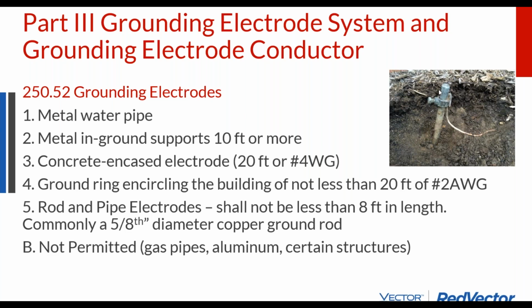These ground rods are 8 feet, 10 feet long. 8 feet needs to be in the ground. So that's a lot of copper in the ground. There's some alternate ways to make the grounding connection, such as circling the building in smaller concrete. But basically, if you use a ground rod, you get a lot more flexibility in this cable coming off the ground rod. Anything that's like you making something in lieu of using a ground rod is going to require more copper.